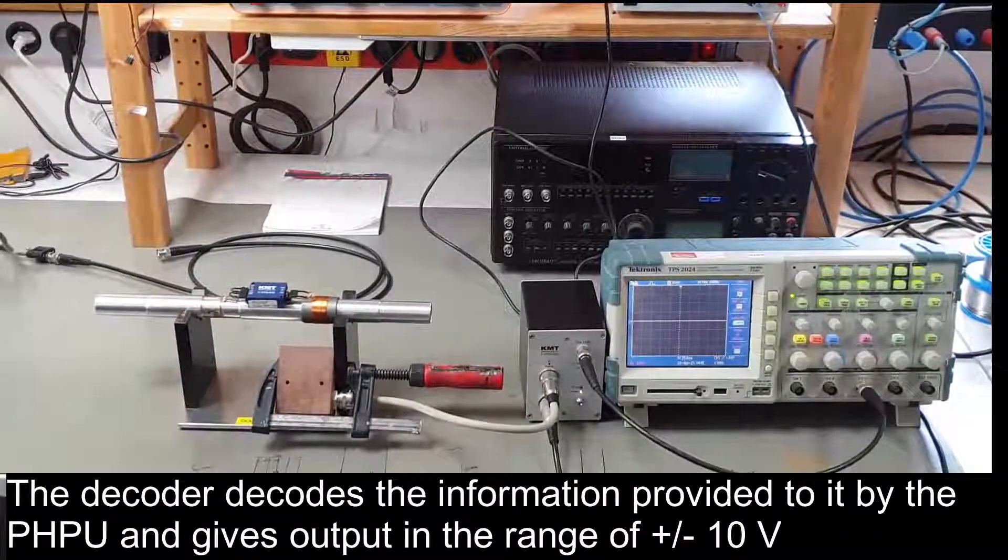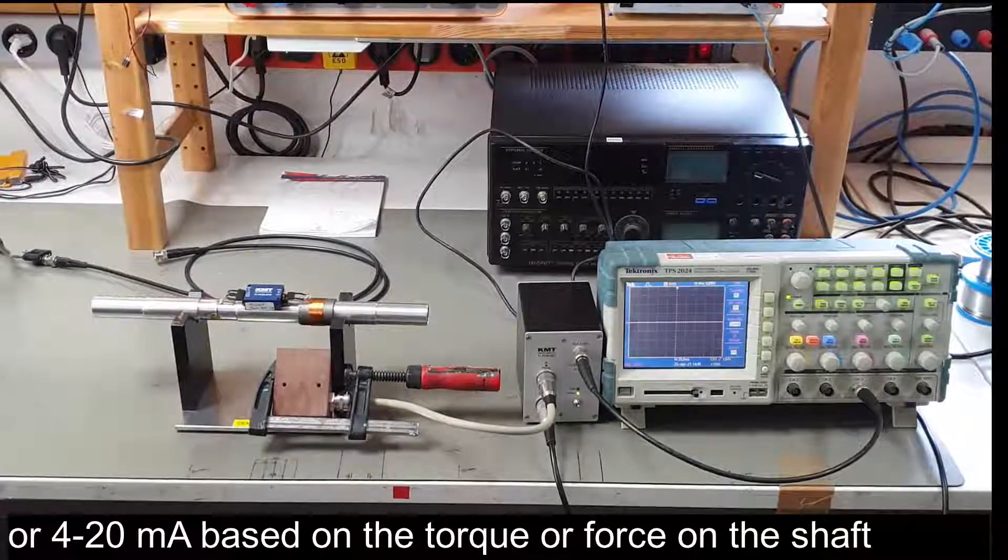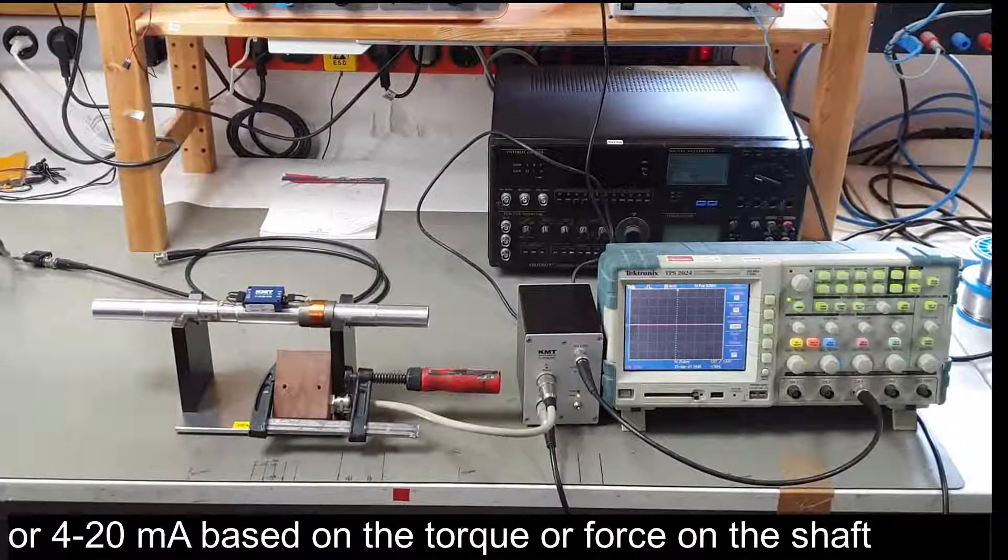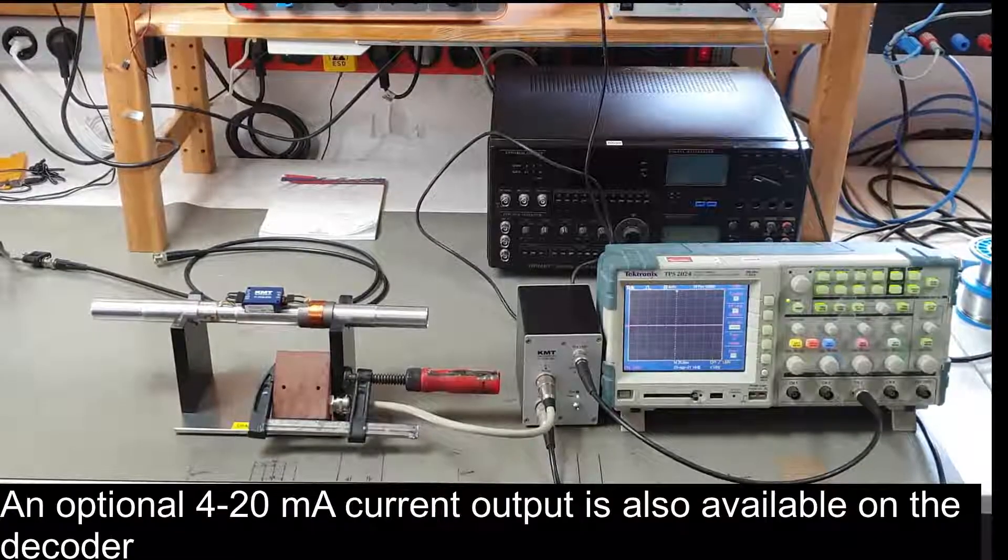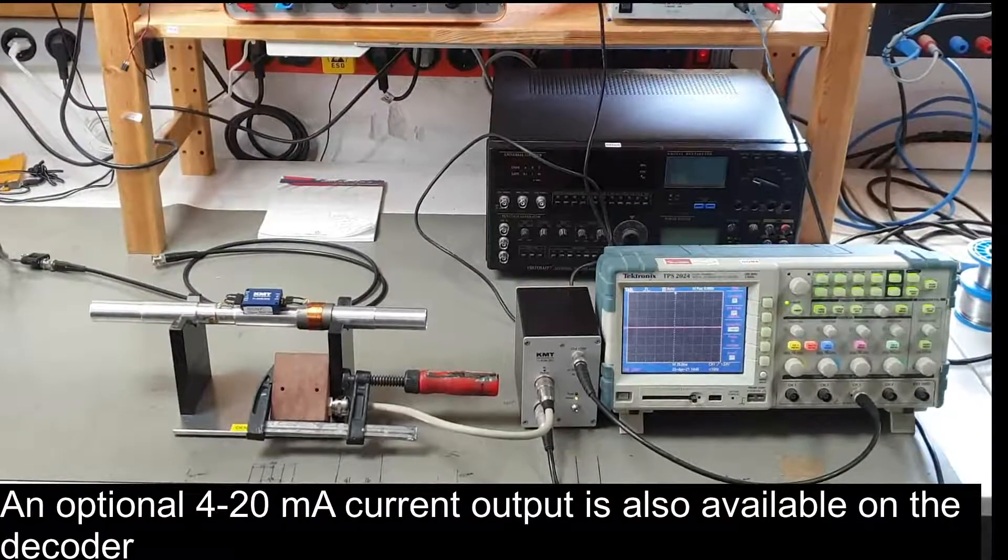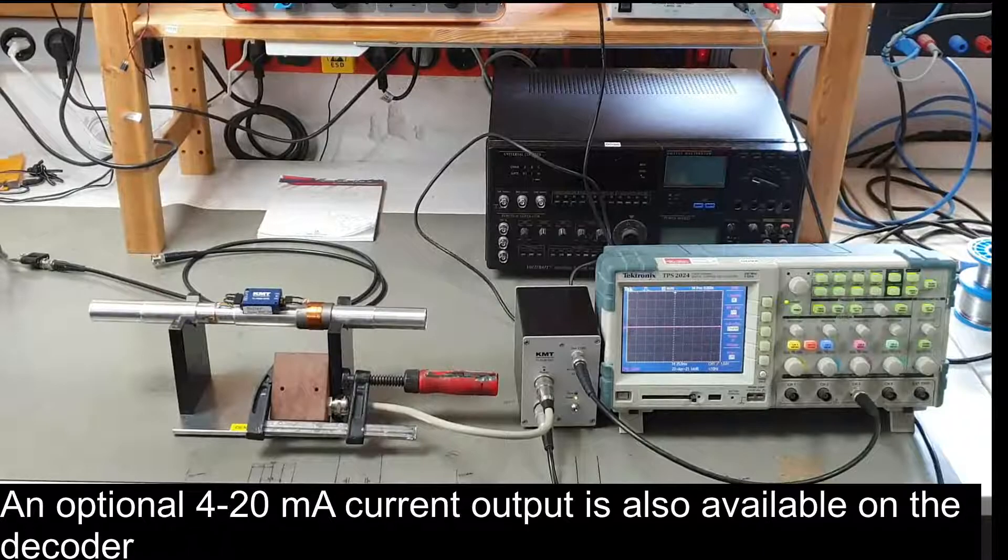The decoder decodes the information provided by the PHPU and gives output in the range of plus/minus 10 volts or 4 to 20 milliampere based on the torque or force on the shaft. An optional 4-20 mA current output is also available on the decoder.